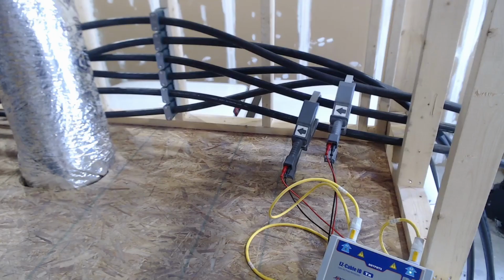All right, so now we're going to show the indirect mode with the CT clamps. So this is when the cable is energized and you can't shut off the cable before you do maintenance on said cable. So now with the CT clamps, we are inducing into the shield into A phase and also inducing into the shield into B phase. Only 2 phases can be identified this way as compared to the direct mode where we can identify 3 phases at a time. Also note, this method can only be done between grounding points on the neutrals of the cables.